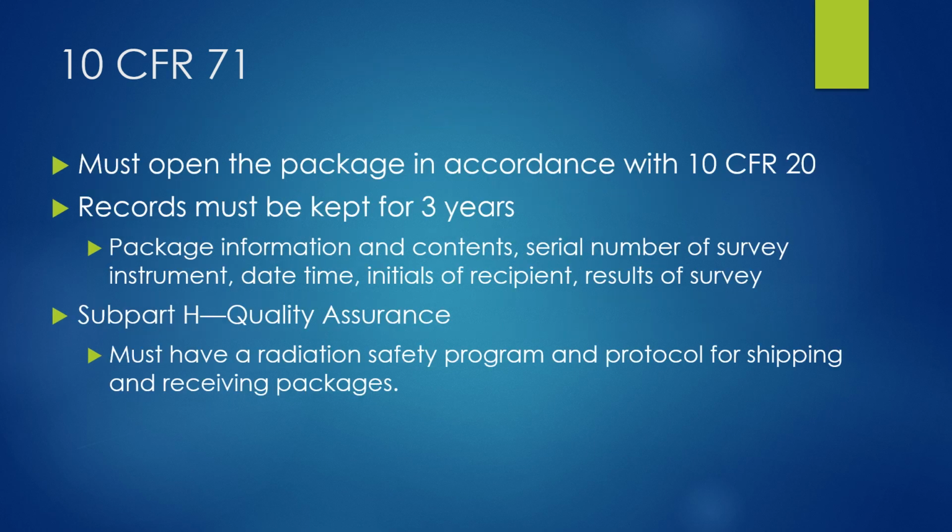Now, 10 CFR 71 is where we have our guidelines for opening a package, but it's also in 10 CFR 20. Remember, when you're opening a package, you always approach it from the outside in. You want to know, is it okay at 1 meter? And then you say, okay, is it okay at the surface? Is it okay to touch it? Is it okay to open it? So you work from the outside in.